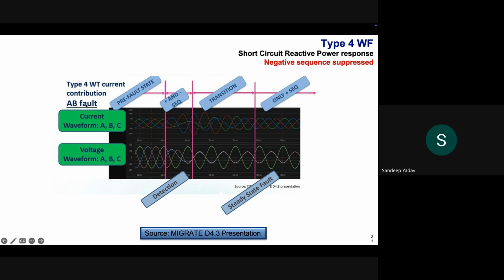So for a phase-to-phase fault, during steady state, after a few cycles, all we will see is the injection of positive sequence current only. And this positive sequence current will not be very different from the pre-fault current in terms of its magnitude. It will be limited by the current limit of the IGBTs, because those are current limited devices, and the maximum value could be 1.1 or 1.2 per unit of the rated current.